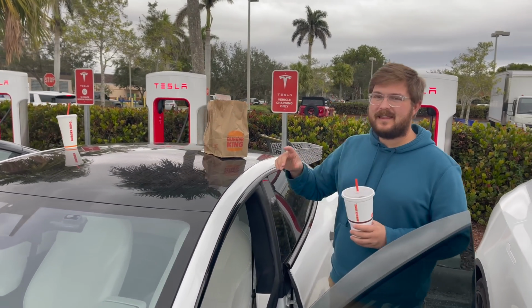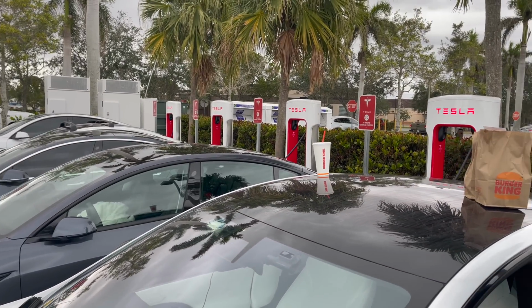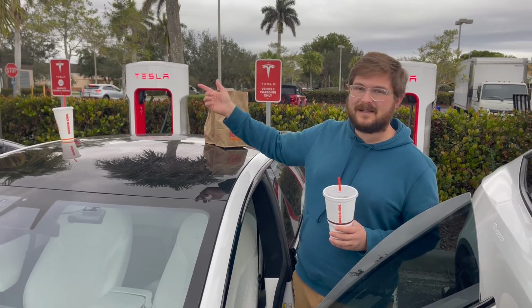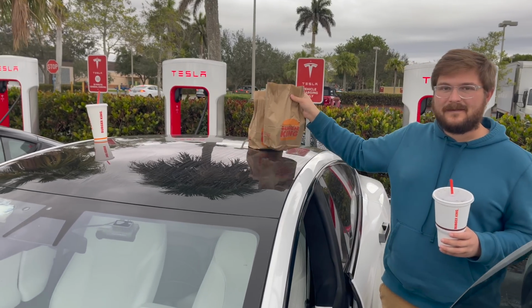We'll take this. The thing is, each one of those is actually about 575 kilowatts. So there's just a little bit over a megawatt available for this full site. So they might be derating us because the cabinets can't output everything. We used to think those were 1 megawatt cabinets. They're actually not. Interesting. Yeah, they do share.